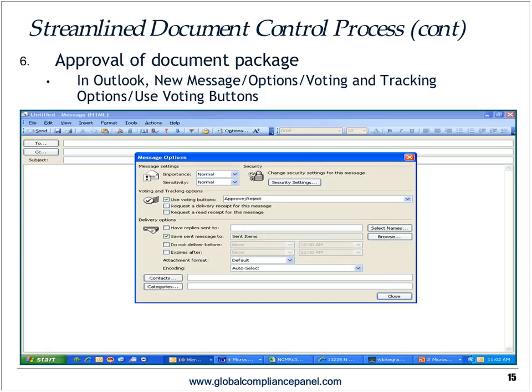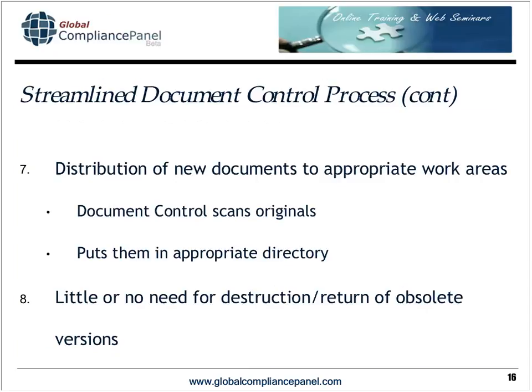Once e-approval is complete, the documents are approved via hand signature — this takes seconds because all documents have already been seen. I want to emphasize: clicking Approve in Outlook is not approval in any regulatory sense. Approval must be via hand signature, or electronic signature under 21 CFR Part 11. What we call 'e-approving' here is simply a streamlined review mechanism, not a regulatory approval.